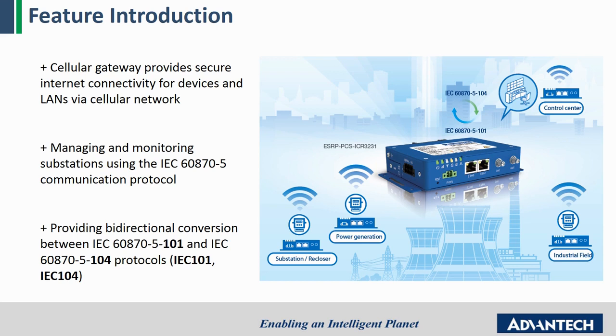On the other hand, new devices primarily use IP networks and Ethernet interface where the IEC 104 version is defined. Today's real energy SCADA applications use the IEC 104 IP version protocol for communication, but at the remote sites are RTUs or PLCs mixed with both protocols 101 and 104 depending on device type.